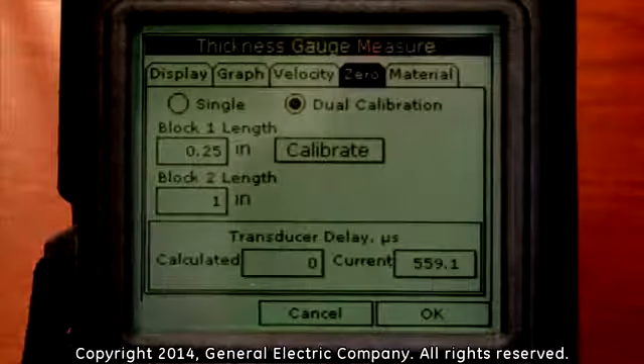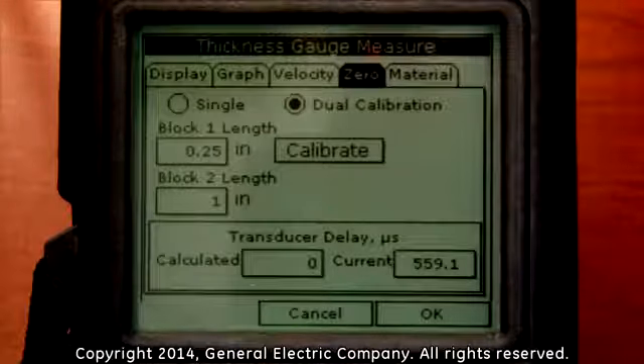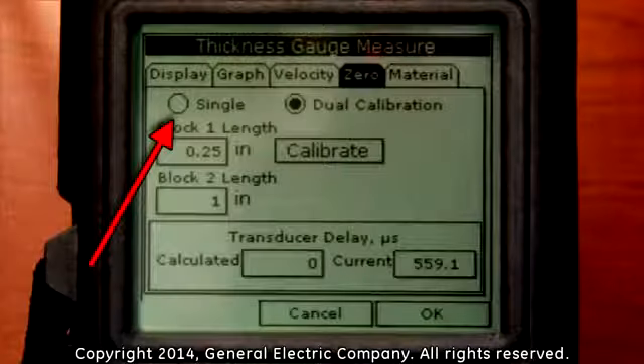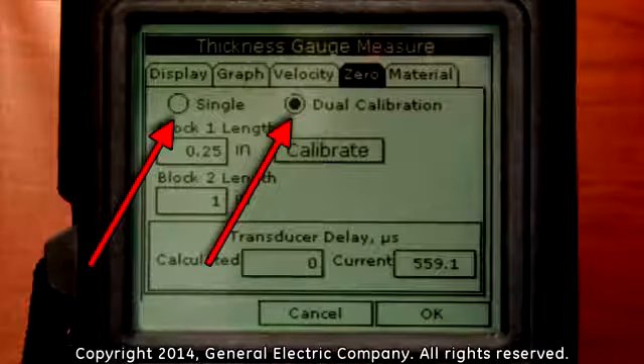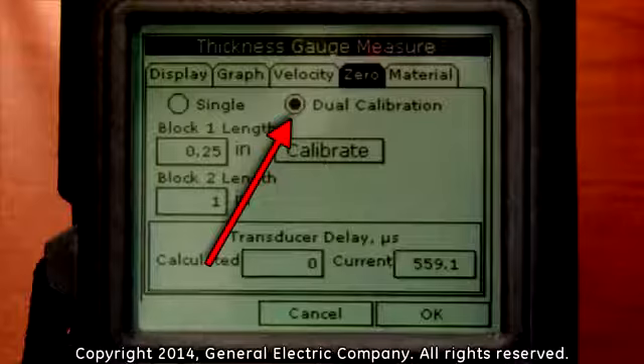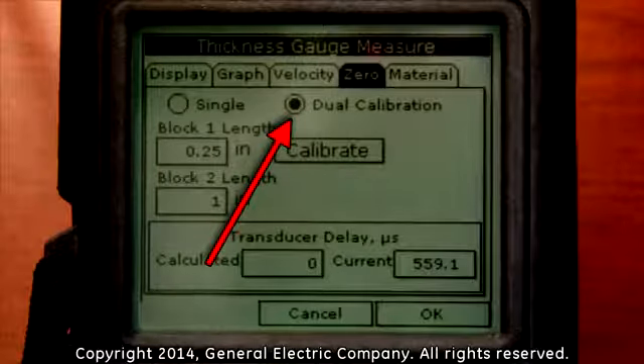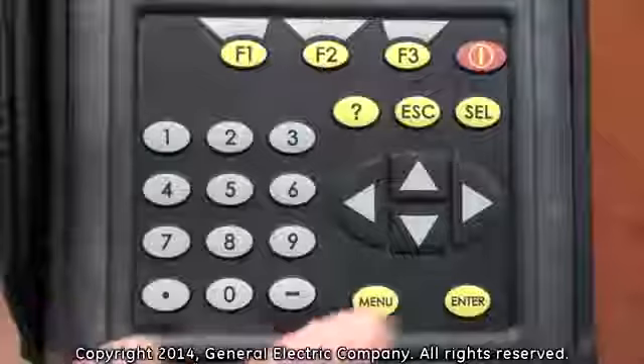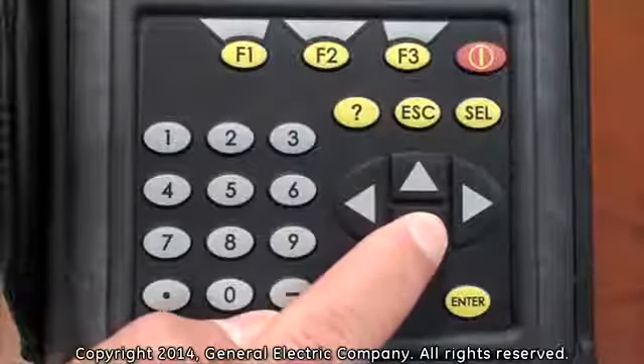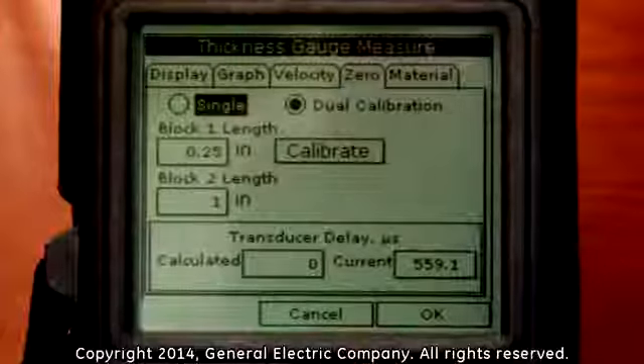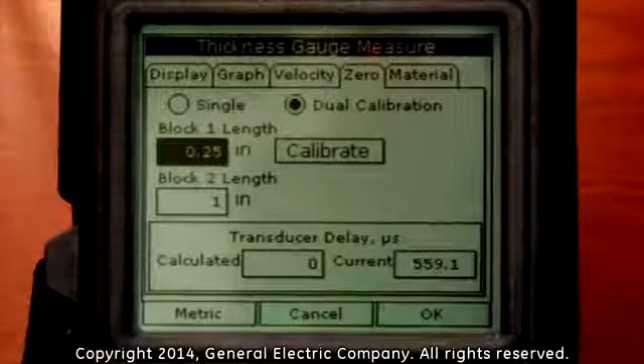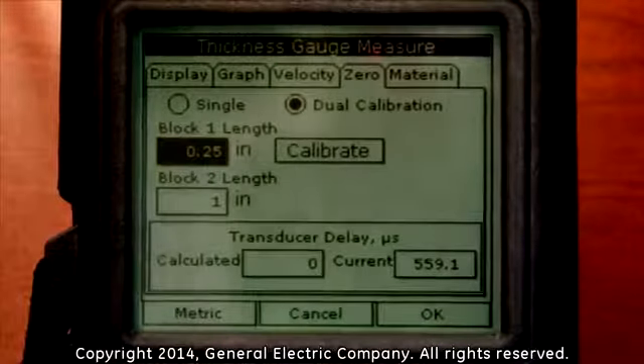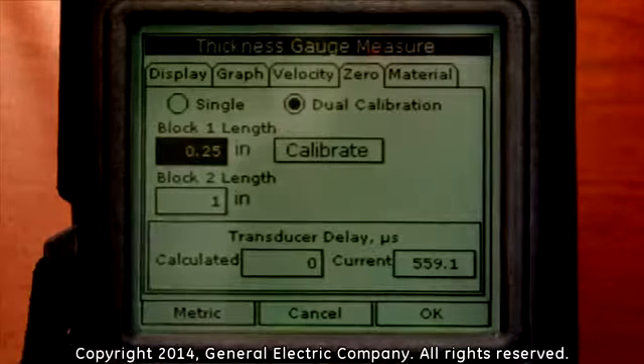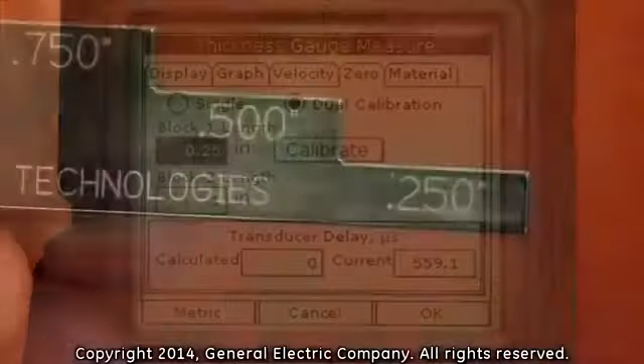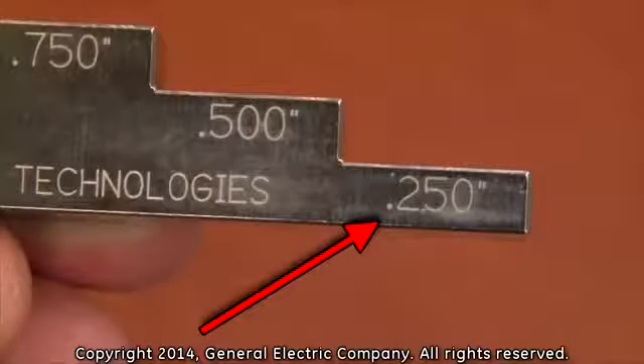At the top of the Zero tab, you will see two options for calibration, the single calibration option and the dual calibration option. The dual calibration option is recommended for calibrating the thickness gauge. Use the down arrow key to navigate down to the block 1 length. You will need to input the thickness of the first measurement you plan to take on your test block. For this example, we are going to use a thickness of 0.25 inches.